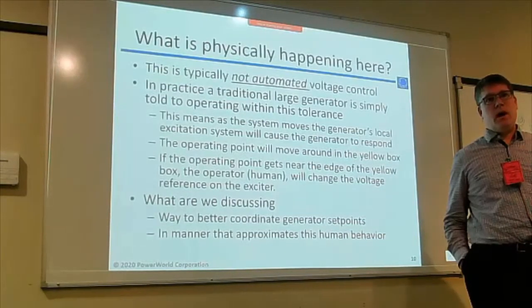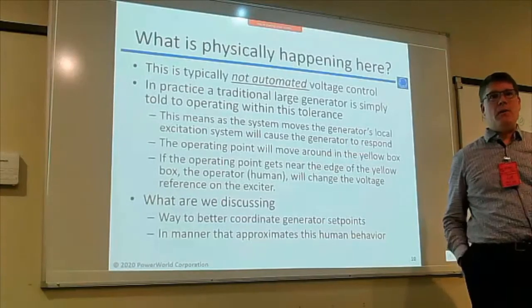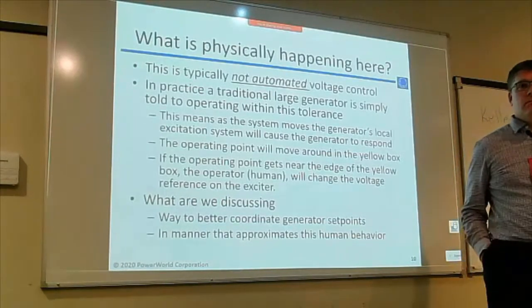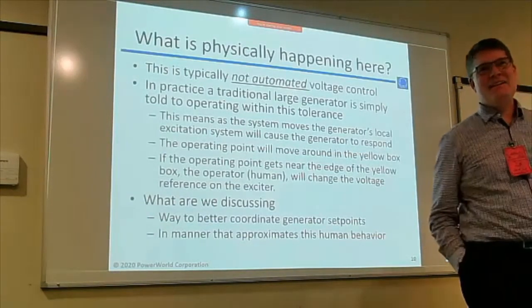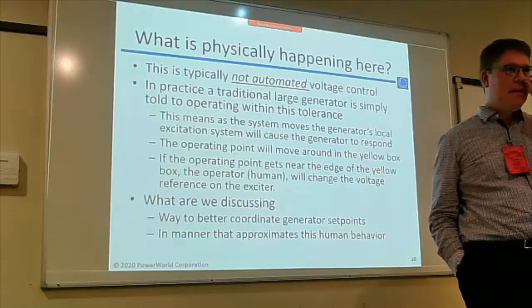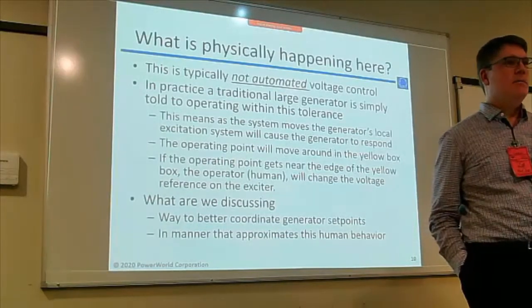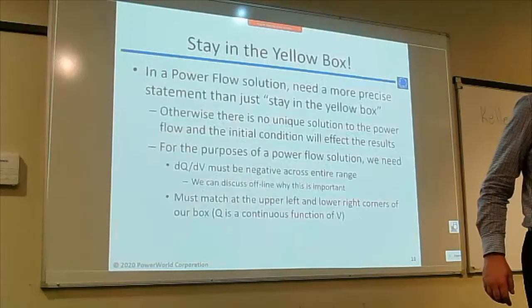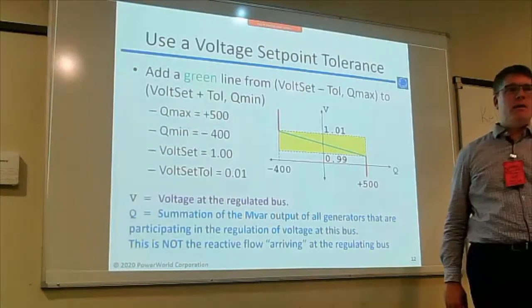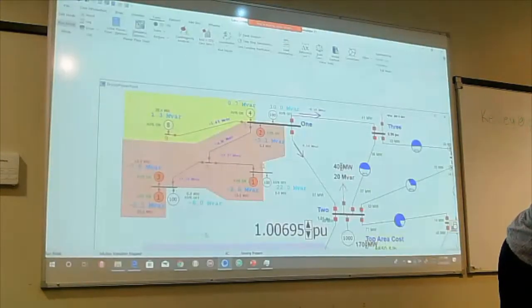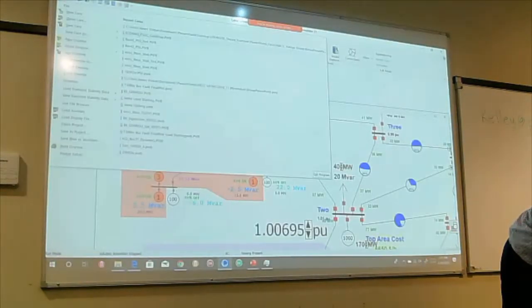Well, the AVR has a set point though, and as system conditions change, it needs to go up or down if it wants the voltage to stay fixed. So the question is, is there feedback there? Okay. Fine to ask them. Most generator folks I ask are like, no, it's the operator hitting the mouse to go up or down. The hydro plants, there's not an operator there, though, right? There is one, okay. Your plants are big enough, they have, yeah.